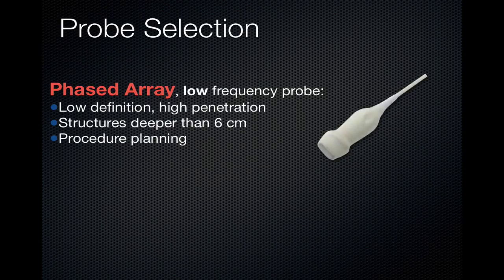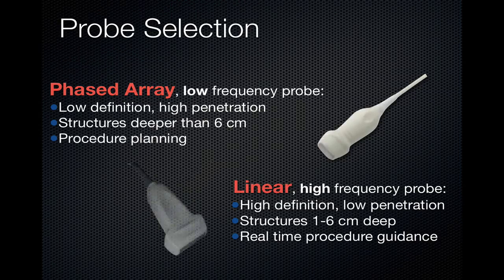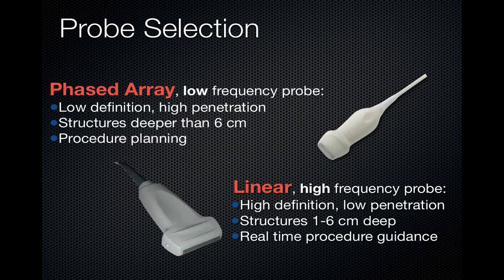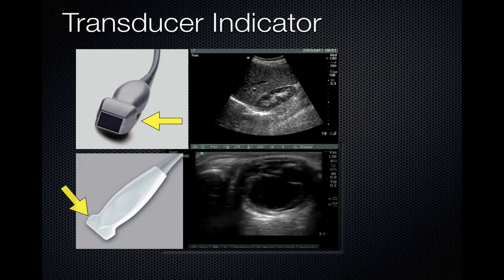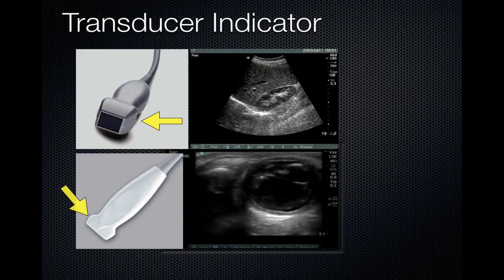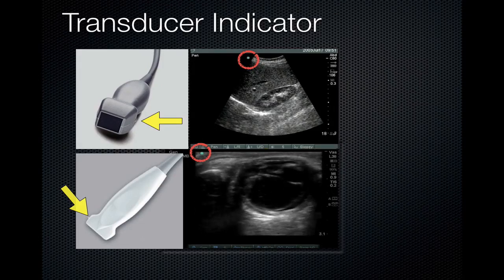Each Sonosite M-Turbo is equipped with two probes, which have different functions. The Phased Array Probe is a low-frequency probe — it provides low definition and high penetration, best for structures deeper than 6 cm, and is used when planning procedures because of the large field of view. The Linear Probe is a high-frequency probe providing high definition but low penetration, best for imaging structures 1 to 6 cm deep. Each transducer has an indicator or orientation marker on one side, used to align with the dot on the screen to help the user determine direction.